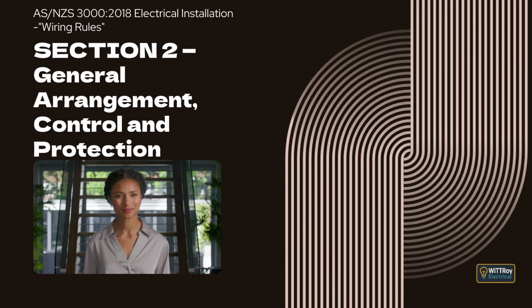Clause 2.7.3, Protection by protective devices. Sometimes we use protective devices to control overvoltage. These devices limit the sudden voltage rise to a level that the installation can safely handle. They must operate fast enough to keep the voltage below the insulation strength of the equipment. They also need to be suitable for the highest voltage that could appear in normal operation, and must not create danger during operation.